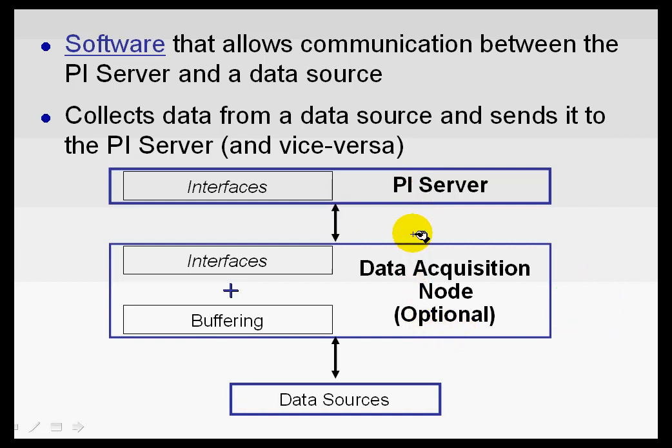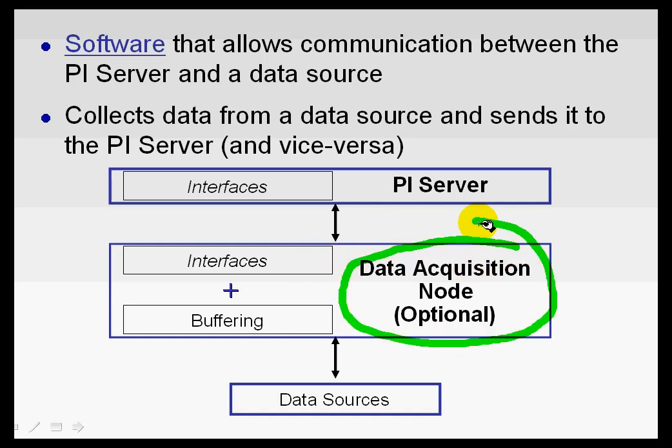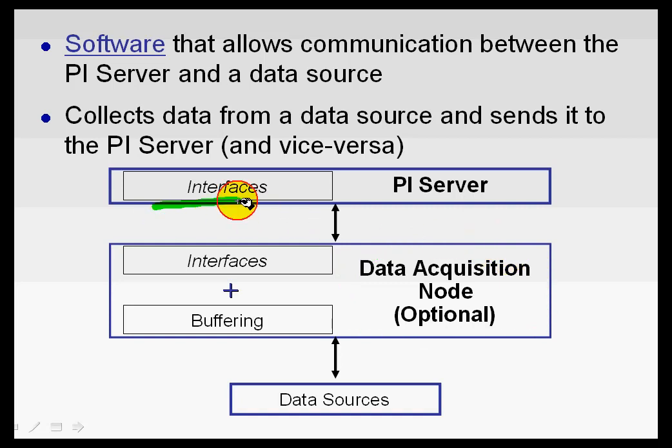Now, as we see here in this drawing, the interface does not have to run on this data acquisition node, which is labeled optional. You can run an interface on the PI Server itself. Typically, we don't recommend that because this is a PI Server that may have hundreds of users. And that's not the best platform to use for high-speed data collection.